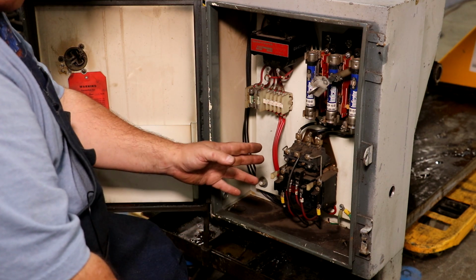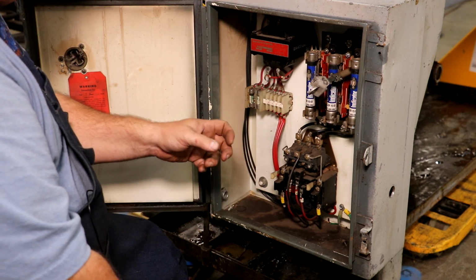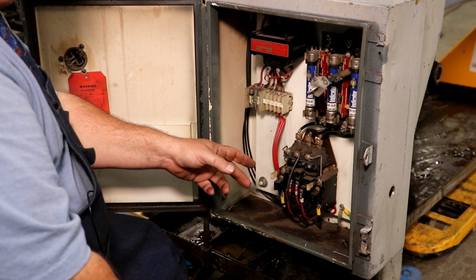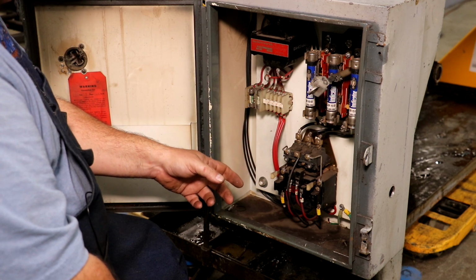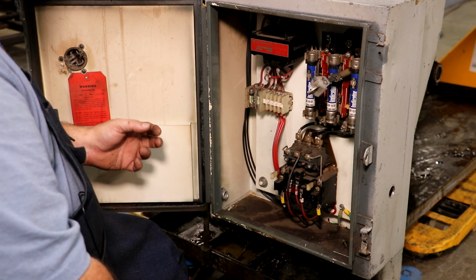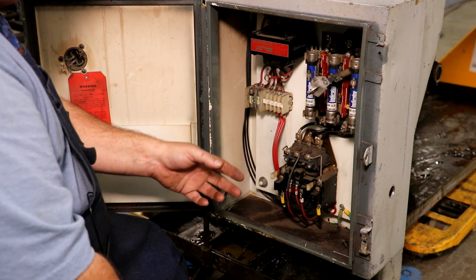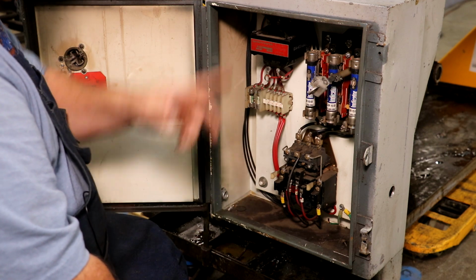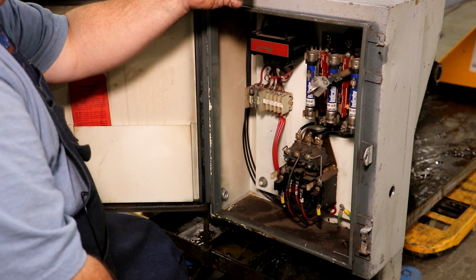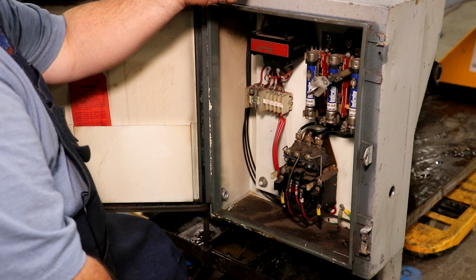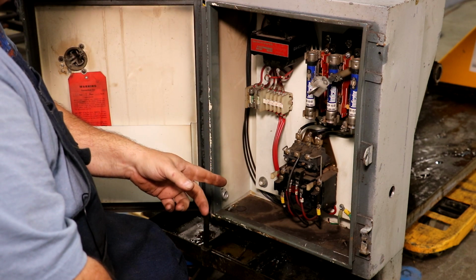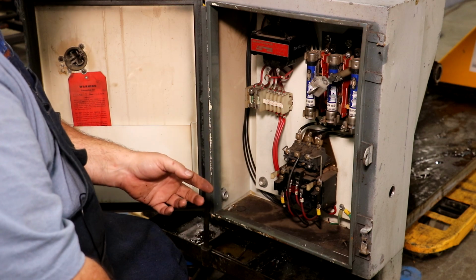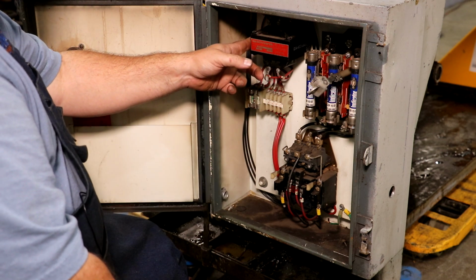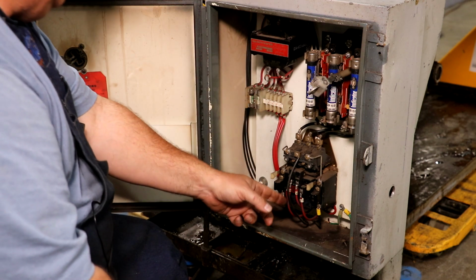Typically we don't like running those push buttons off of line voltage, because if this thing was still hooked up on 480 volts, you'd have 480 volts going to the buttons up there. That would be a potential place you could get shocked. So this steps down the voltage that goes to the coil.